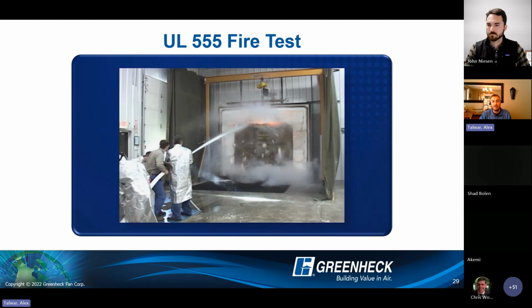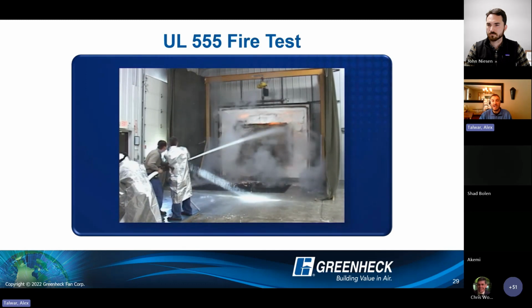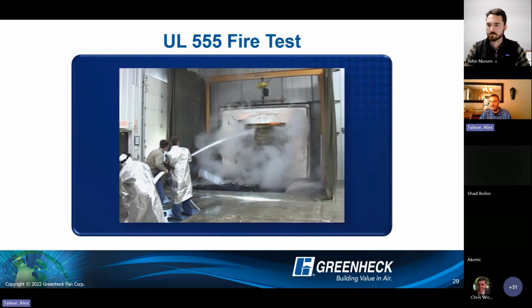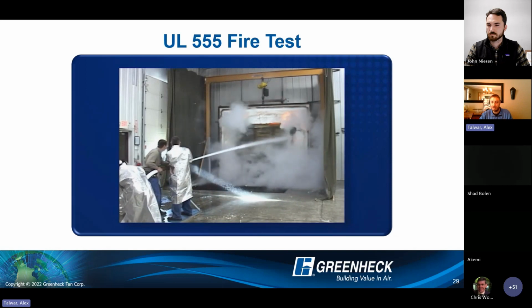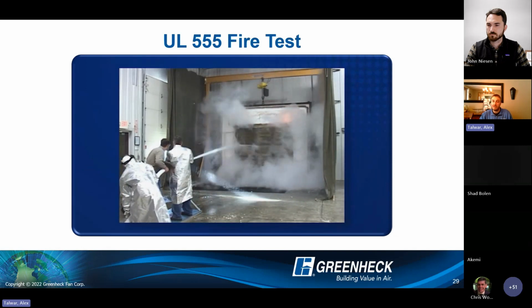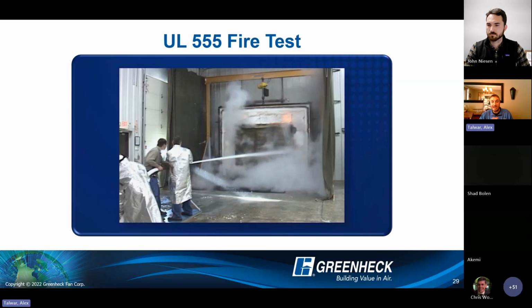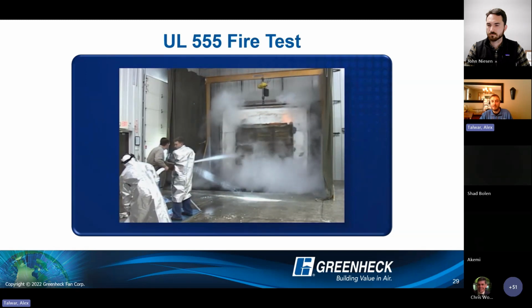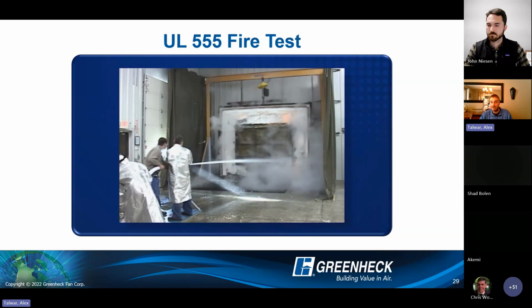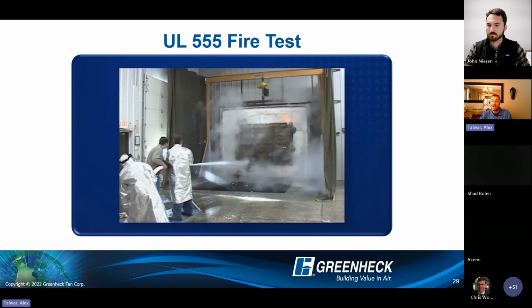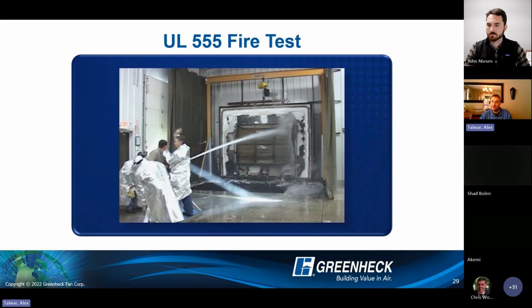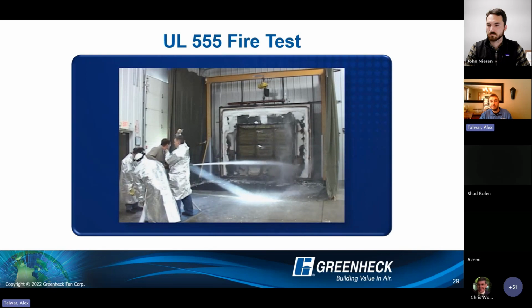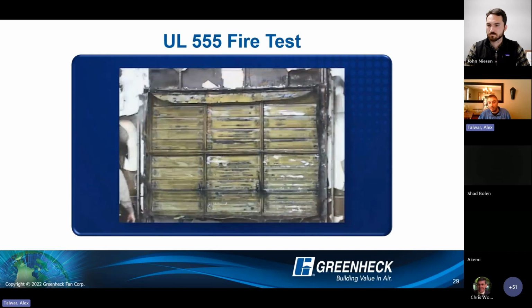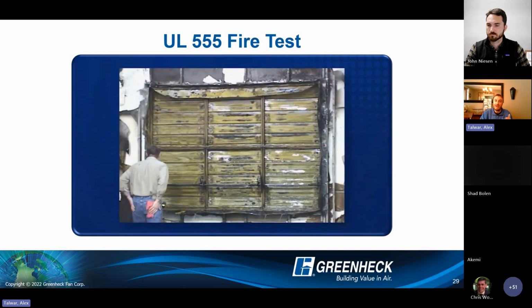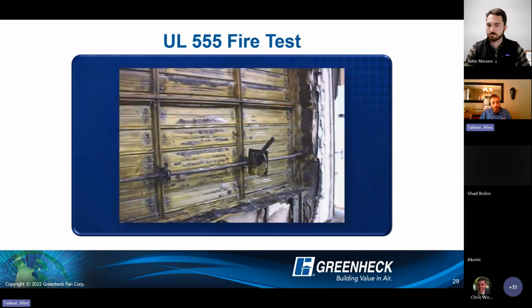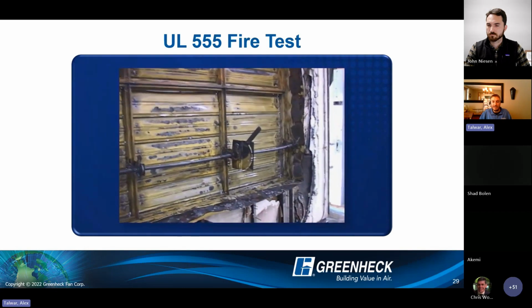But this hose stream, this is all part of the test as well. So after being subjected to that time temperature curve, which gets up to almost 2000 degrees by the end of the test, now we're hitting it with a 30 PSI hose stream for the 1.5 rating. And it's actually a 45 PSI hose stream for the 3-hour rating. So this is really the most difficult part of the test here, is hitting it with the impact of that water, temperature shock, all that kind of stuff.